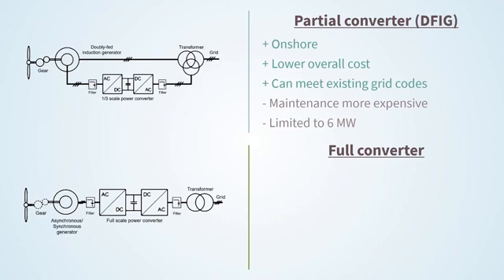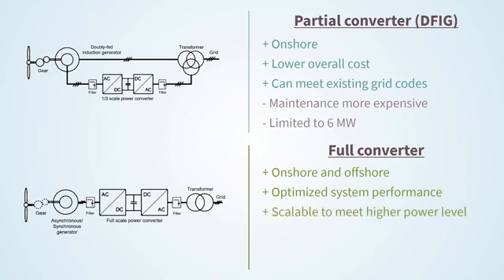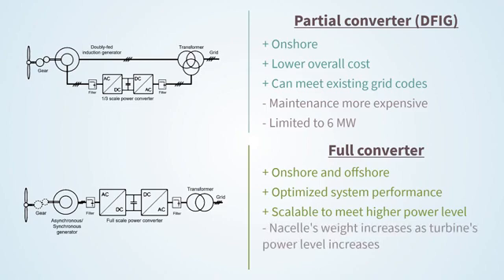On the other hand, the permanent magnet synchronous generator can be used on onshore and offshore turbines, has an optimized system performance and is easily scalable to meet higher power levels. The downside is that nacelle weight increases as the turbine's power level increases and cost is higher than DFIG turbines.